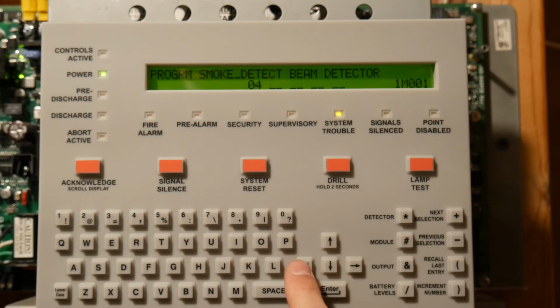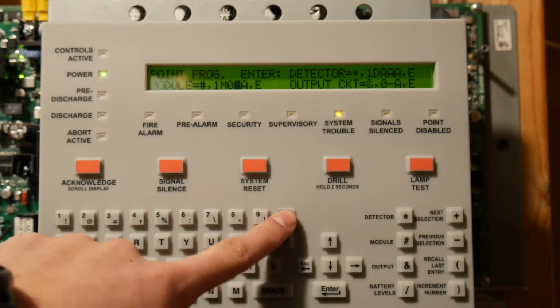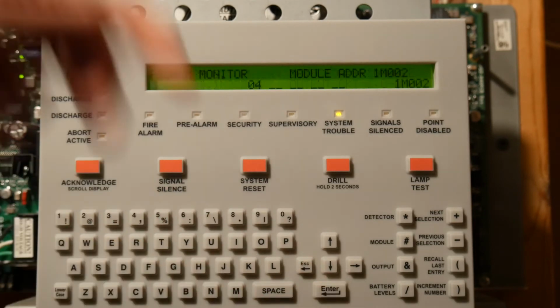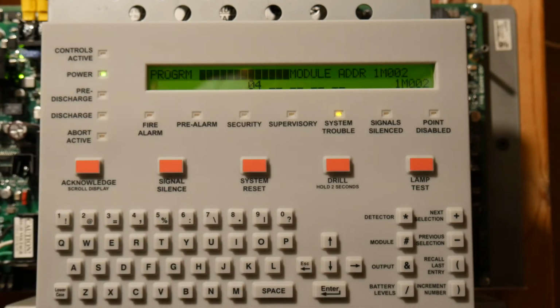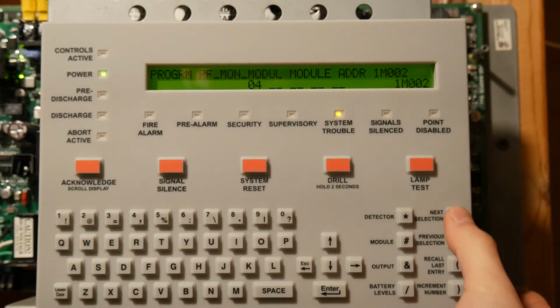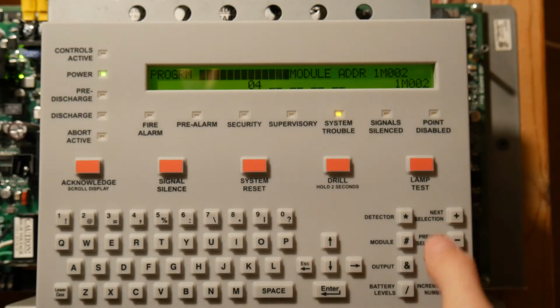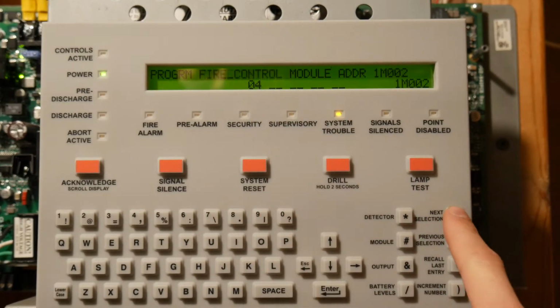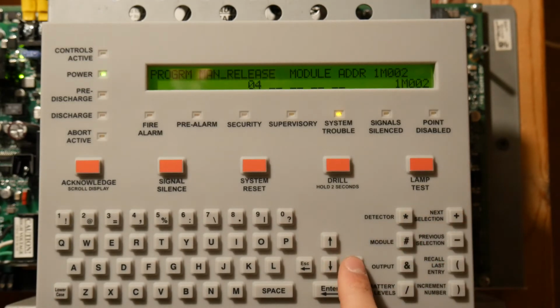Zone 1 is for my pull stations and my alarm modules. Anything that's not a detector, I have it set as zone 1. So module 002, I have it set as an agent release. So we're going to next selection. Also, you could change your selection by using the button. Plus and minus are for changing what that is. Manual release. Okay. Now we're going to set this as agent release.